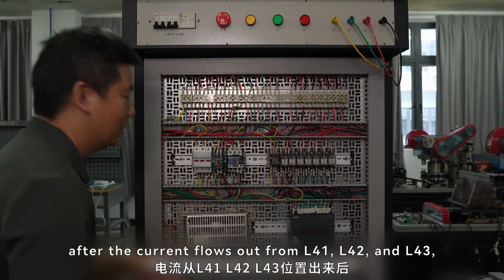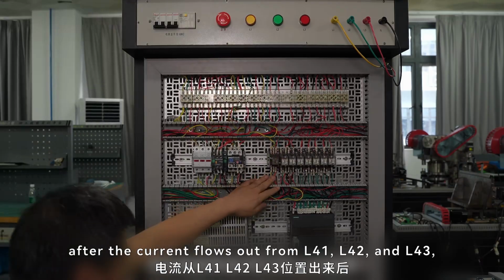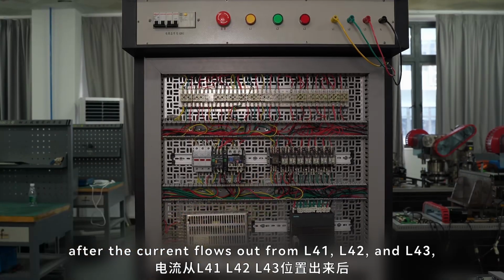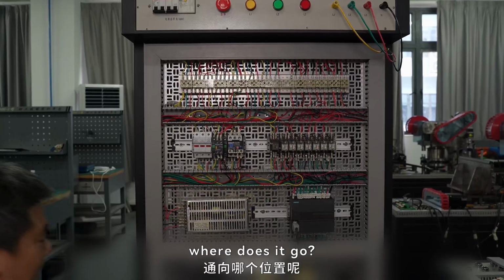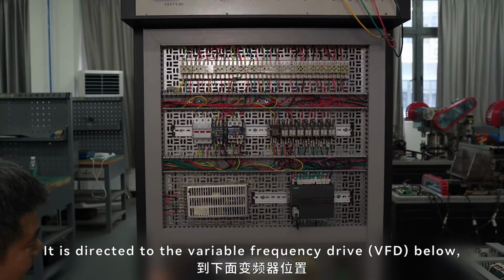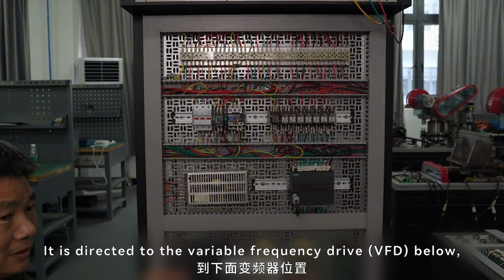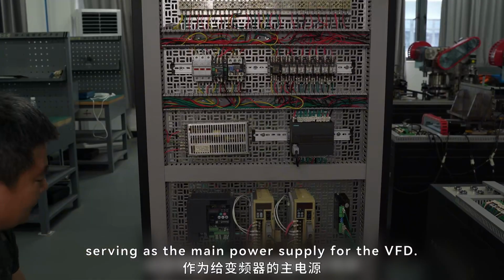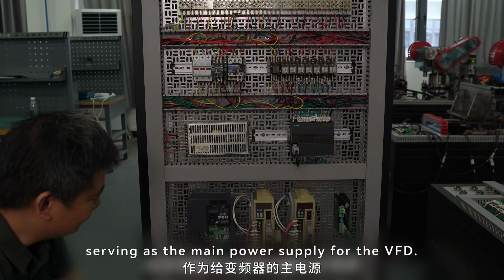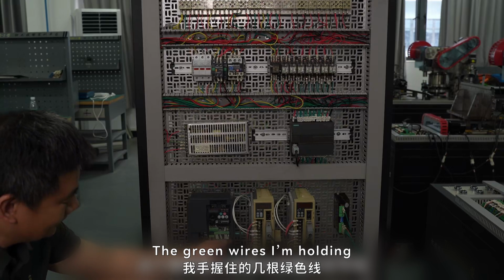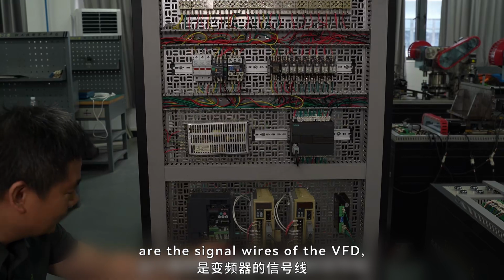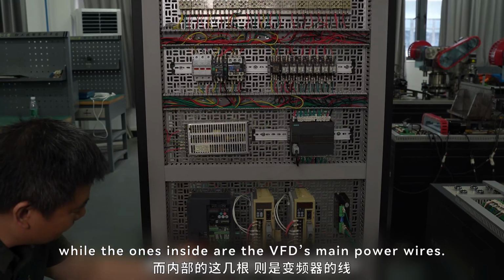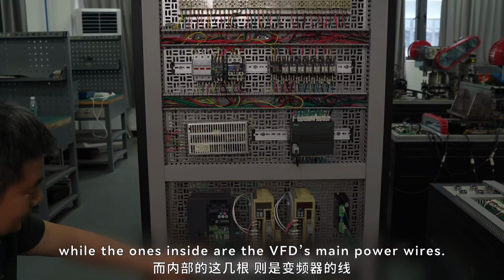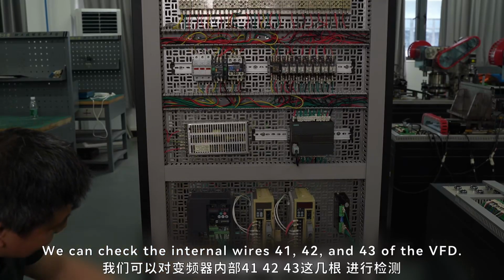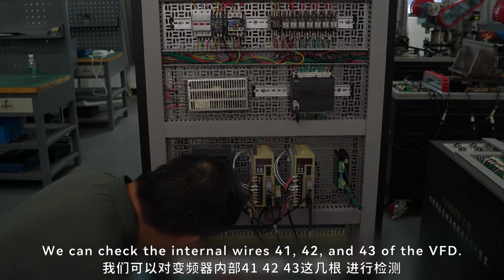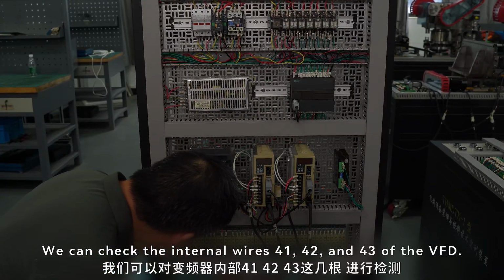Next, after the current flows out from L41, L42, and L43, where does it go? It is directed to the variable frequency drive, VFD below, serving as the main power supply for the VFD. The green wires I'm holding are the signal wires of the VFD, while the ones inside are the VFD's main power wires. We can check the internal wires 41, 42, and 43 of the VFD.